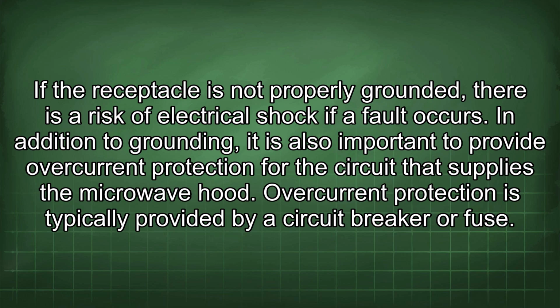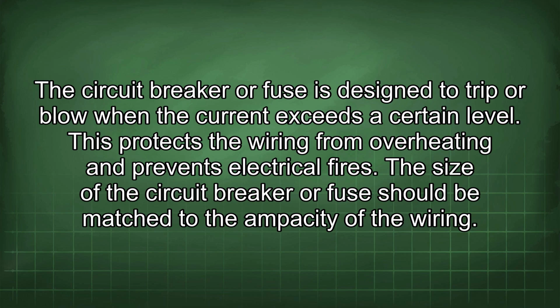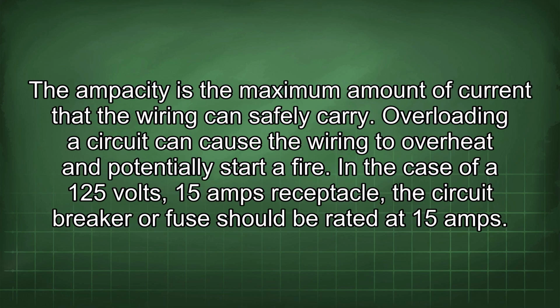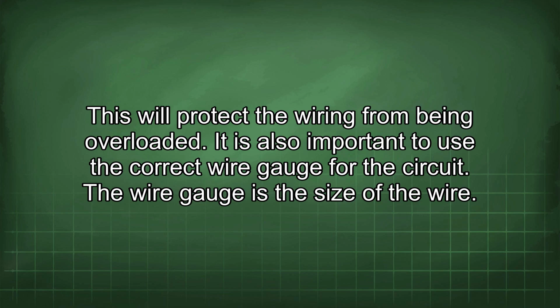In addition to grounding, it is also important to provide overcurrent protection for the circuit that supplies the microwave hood. Overcurrent protection is typically provided by a circuit breaker or fuse. The circuit breaker or fuse is designed to trip or blow when the current exceeds a certain level. This protects the wiring from overheating and prevents electrical fires. The size of the circuit breaker or fuse should be matched to the ampacity of the wiring. The ampacity is the maximum amount of current that the wiring can safely carry. Overloading a circuit can cause the wiring to overheat and potentially start a fire. In the case of a 125 volts, 15 amps receptacle, the circuit breaker or fuse should be rated at 15 amps. This will protect the wiring from being overloaded.